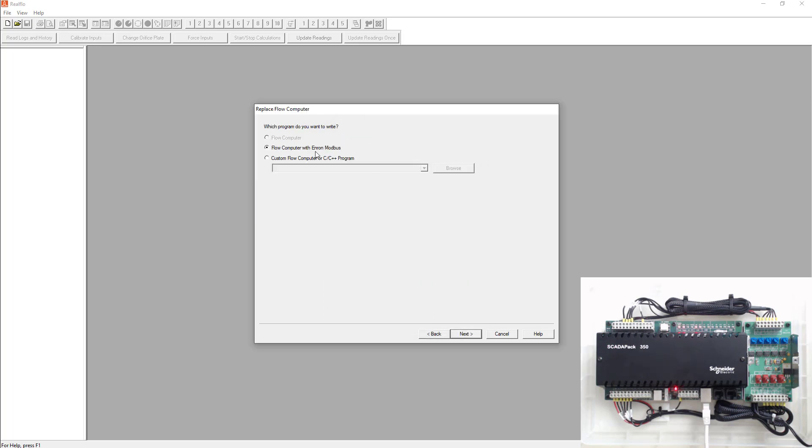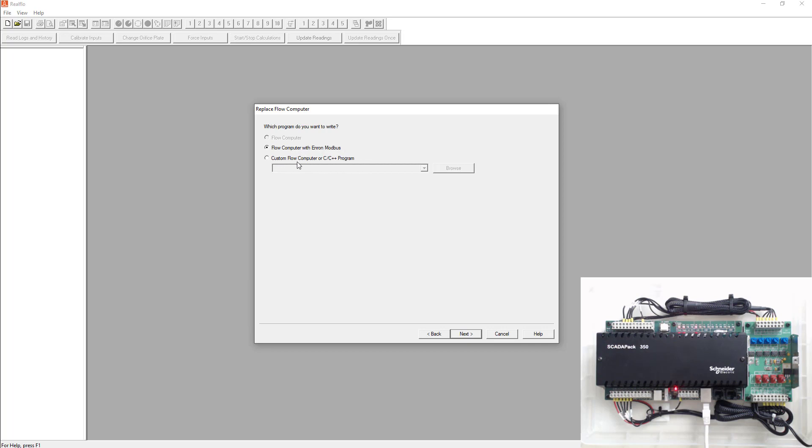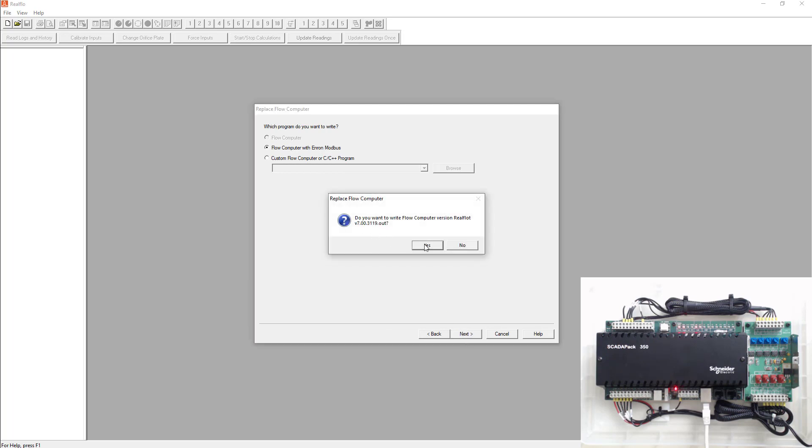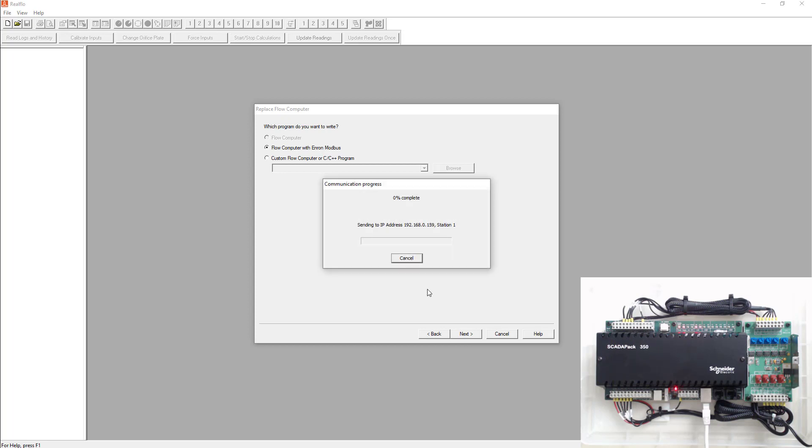It connects to the SCADA pack and realizes there's no C program in that SCADA pack so it's asked you do you want to write the C program. You can either write the flow computer with Enron Modbus so that means it'll write the latest and greatest version of RealFlow or you could pick an older version or a custom version that you've created. So I'm going to write the latest and greatest and go next. And it'll ask you do you want to write flow computer version 7. I'll go yes. And now this will take a little bit so I'm just going to go ahead and fast forward the video a little bit here.